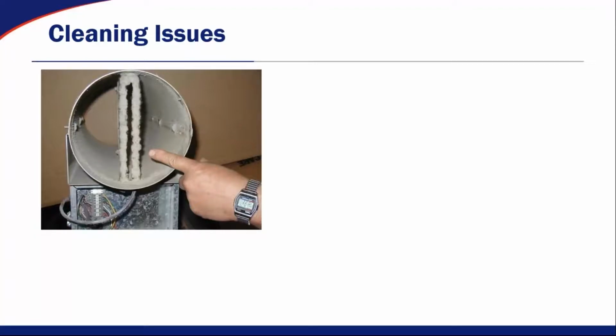We can look at some other scenarios. This particular valve was a clean, quote unquote, general exhaust valve in an animal holding area. And what you see on that flow sensor is actually the dirt and the dust and the lint that's in the clean air for the general exhaust air. This is not the cage rack exhaust valve. This is just general exhaust, clean air. And that sensor got clogged up in about 9 months of normal use, just taking animals in and out of their cages, giving them their shots and putting them back in. So you can just imagine how that would work after 9 months.